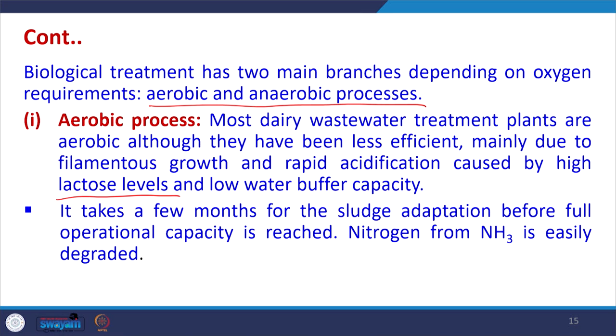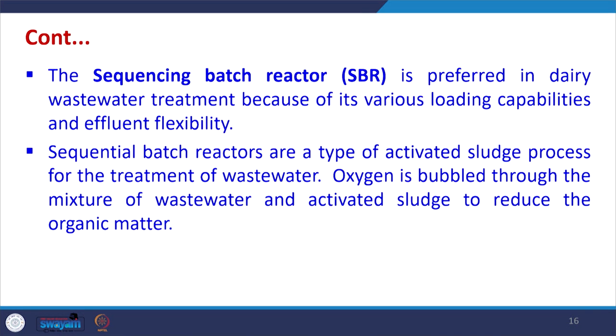Nitrogen from ammonia can be easily degraded using aerobic processes. The sequential batch reactor is the preferred technology for aerobic dairy wastewater treatment because it has the capability of accepting various loading capacities and can treat effluents of a flexible nature. If aerobic treatment is adopted, SBR is one of the preferred techniques.